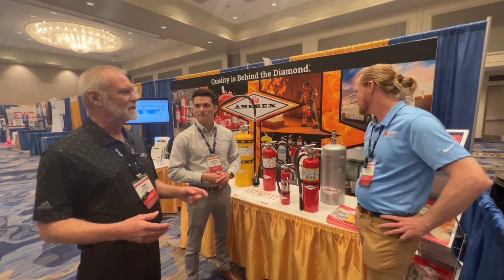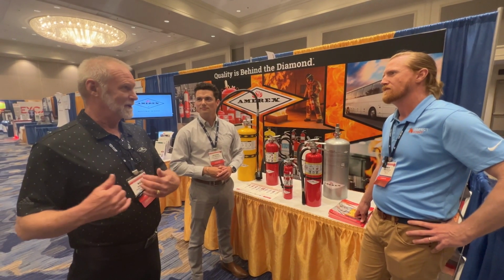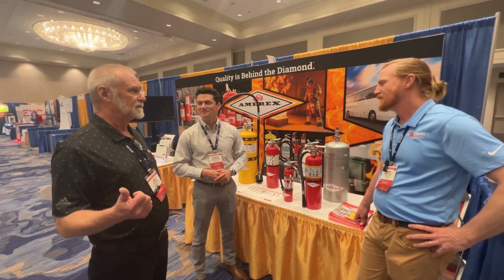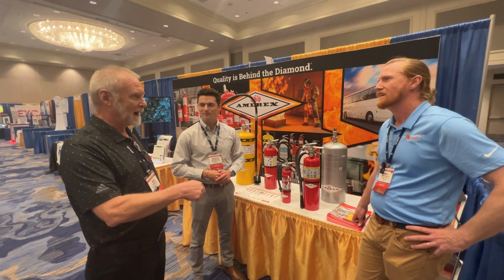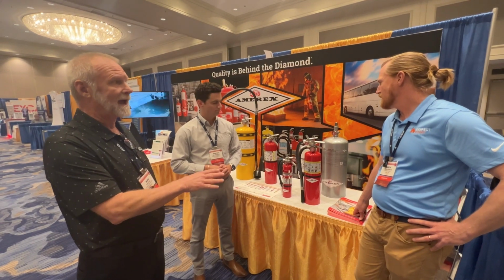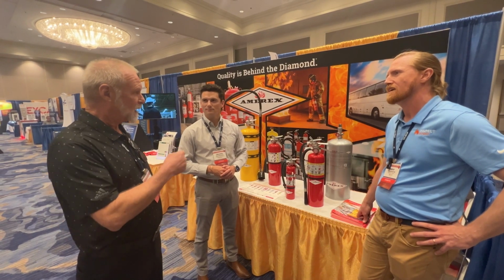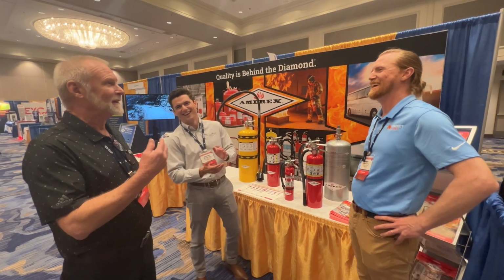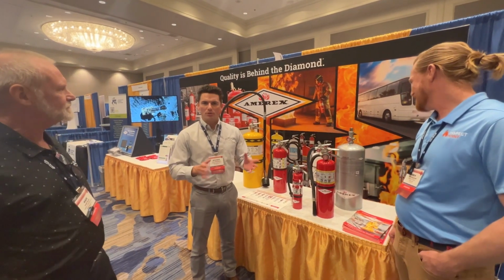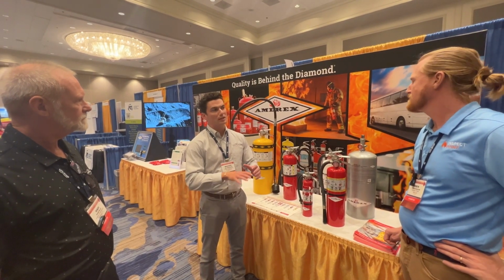That UL verification is a really important piece of the puzzle. I can remember in my territory, because I have the Southern Louisiana territory, the offshore guys really wanted to know that what they're going to be buying is going to hold up. So in addition to having the 12-year warranty like we had all along, we now have this verification process. Brayden knows way more about that than I do, so I'm going to let Brayden tell what that verification process is. You go through the UL 299 salt fog testing. That's the typical corrosion testing you're going to see with any kind of standard unit.